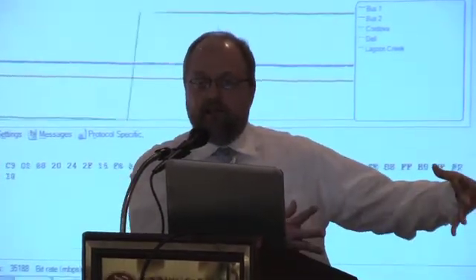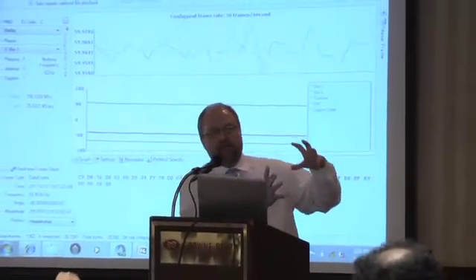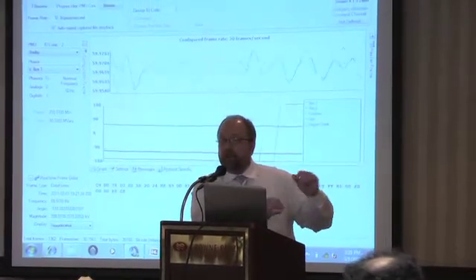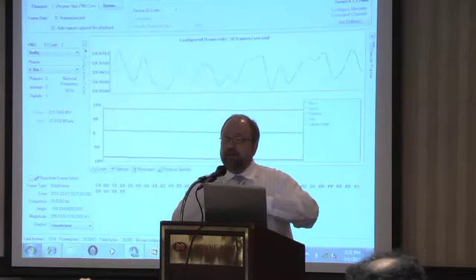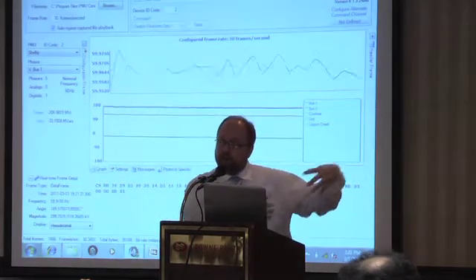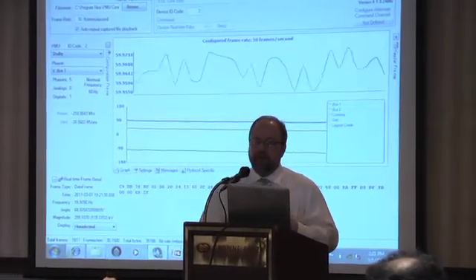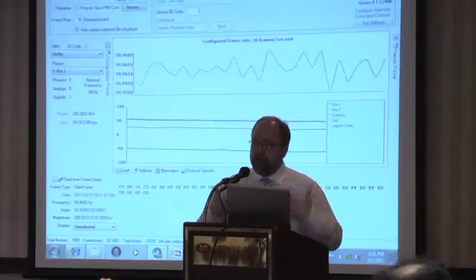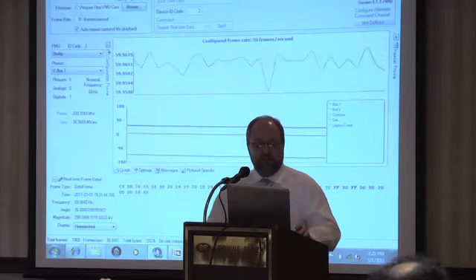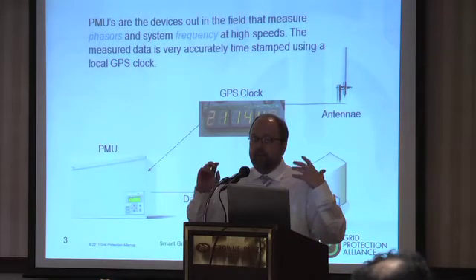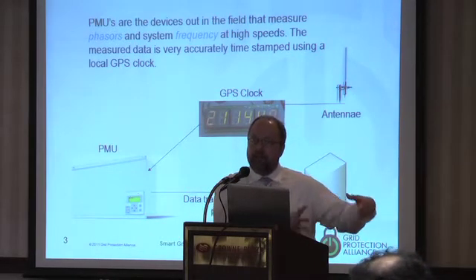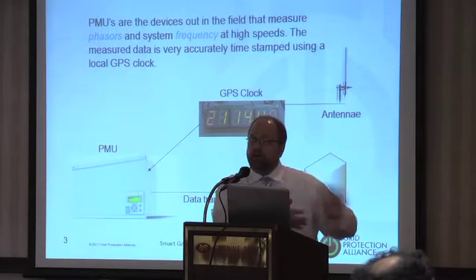It's this moving picture of information that you need to be able to see, so you can really analyze and see things you've never seen before. If you had this information early on, these become early detection mechanisms for preventing blackouts. In a lot of the blackout investigations we've had in the past, we had almost an hour or two of notice sometimes if you started watching the angles — but we didn't have any way to effectively measure the angles and look at them relative to each other. After they happen, we'll be able to figure out what happened very quickly, and then develop algorithms to put alarms into the system and allow operators to act more quickly.